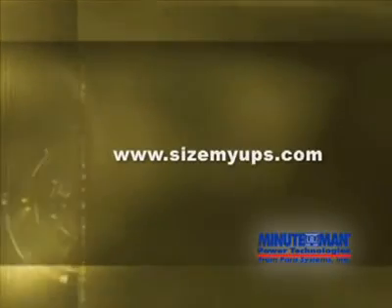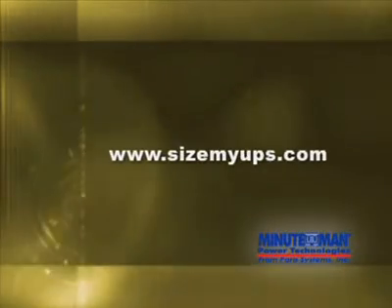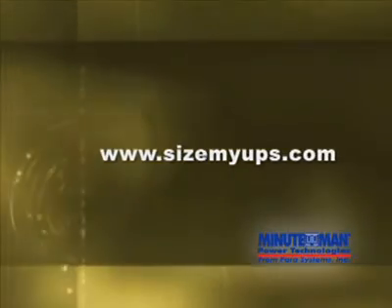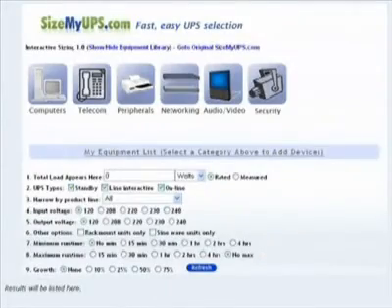I know it can be a daunting task to select the proper UPS. You may get intimidated and you don't know which one to recommend. Minuteman UPS recognized that, and we came out with a website that is very simple to use. It's called Size My UPS. If you know your load in watts, VA, or amps, you can just plug it in and you can put, hey, I need 2 hours worth of backup. And it'll actually narrow down the list and it'll tell you exactly which uninterruptible power supply to use.